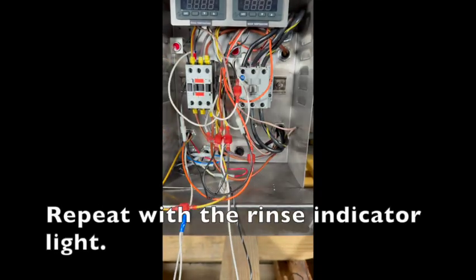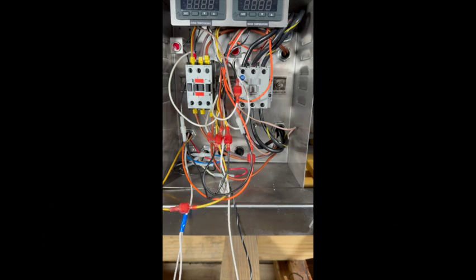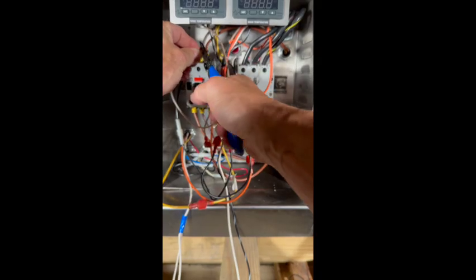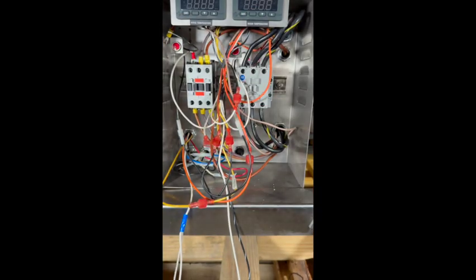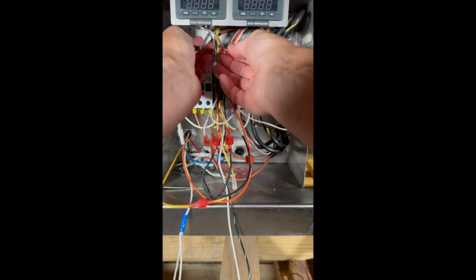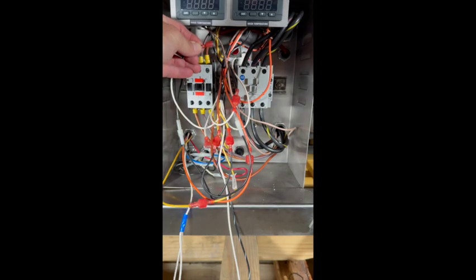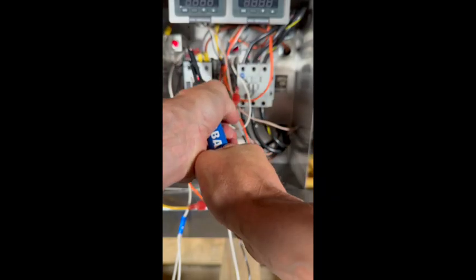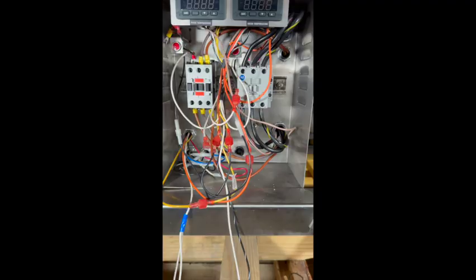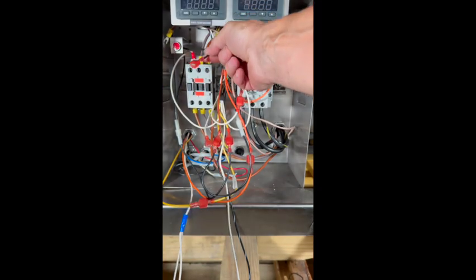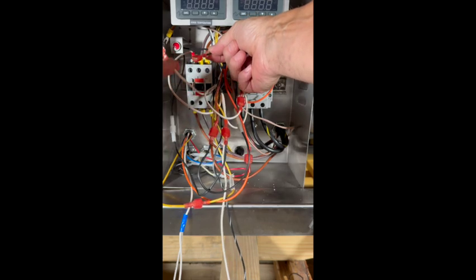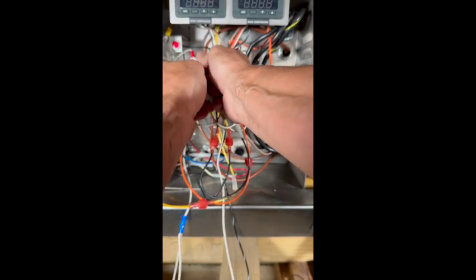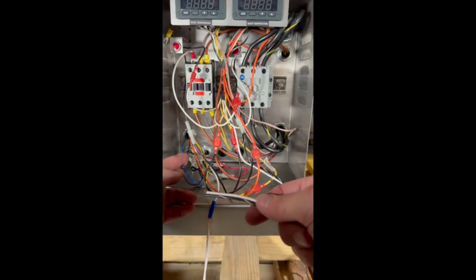And we're going to do the same thing on the rinse side. You're going to need to prepare that wire, again probably coming from the factory itself. It's probably going to have a terminal on it. So again, we're putting on another terminal, male. And then you're going to find the last remaining wire coming from those control units. It's going to be a white wire, female terminal. You're going to connect those together. So at this point, all your contactors and your lights are all connected.